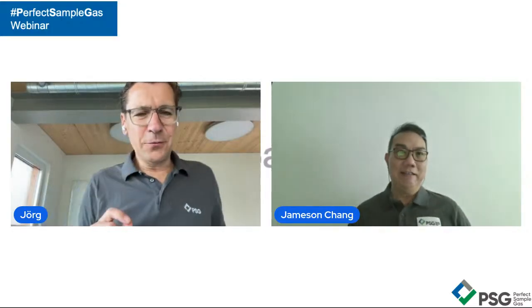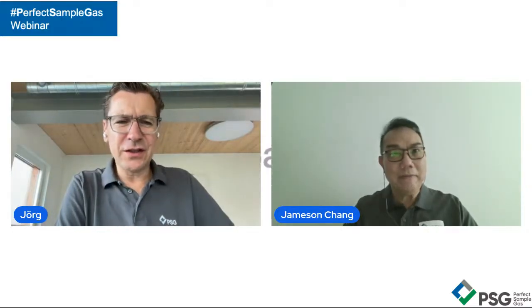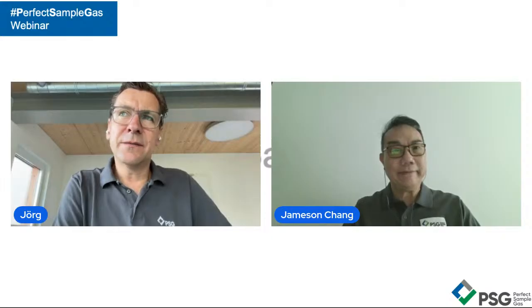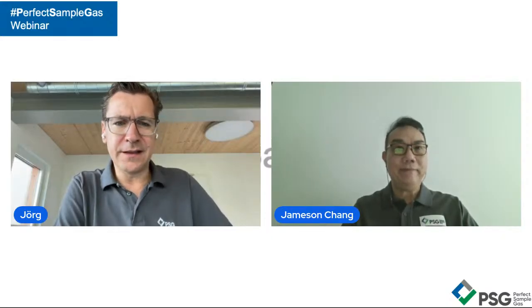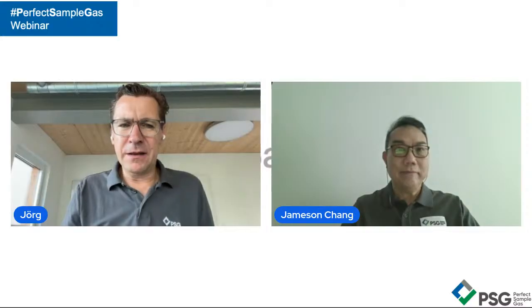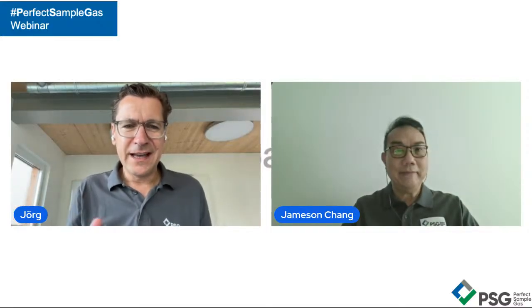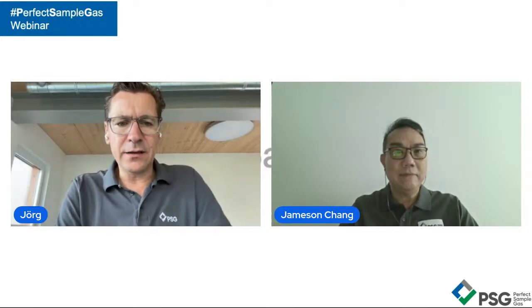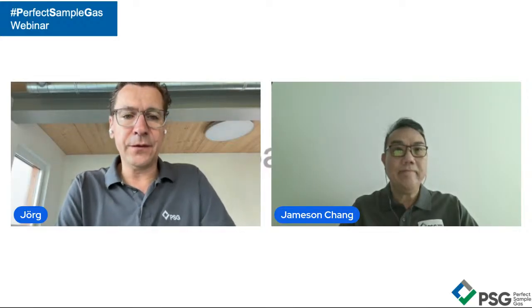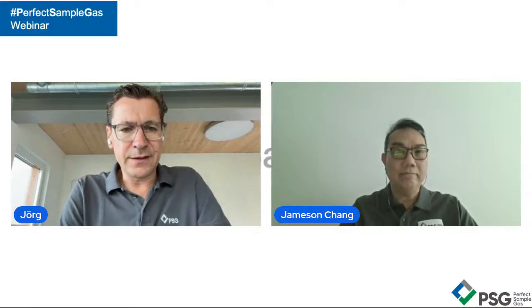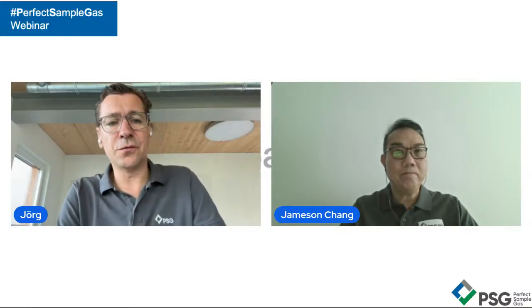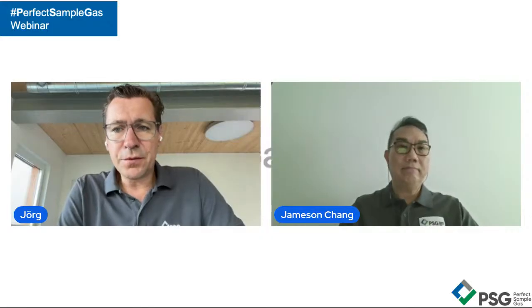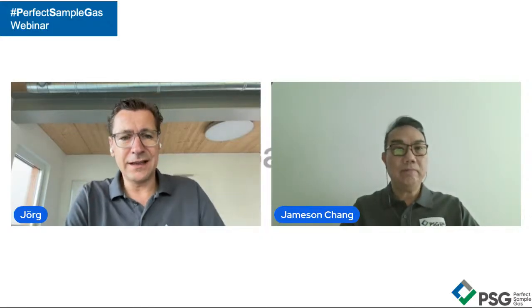That's interesting what you say, Jameson, because sometimes we have discussions that they take some additional filters, some protection equipment, where you think, hey, if you have a proper sampling system, you don't need this. But I can understand, if you are low on the quality of the heated line, you might get condensate, you might get a lot of water if your cooler is not there, or if you even have a hot extractive system where you wouldn't even use a cooler to remove the water, then you want to protect your analyzer because it's very costly equipment, right?